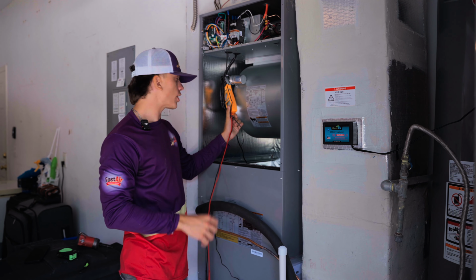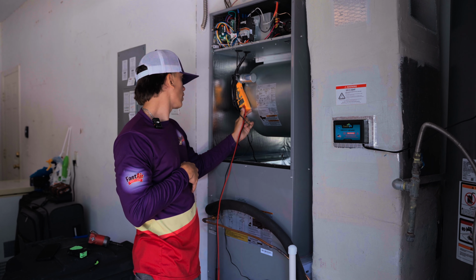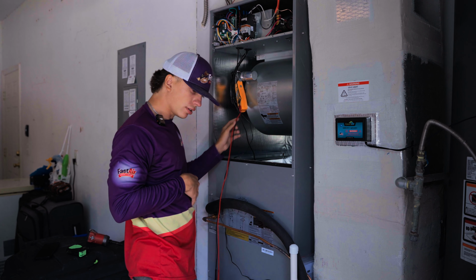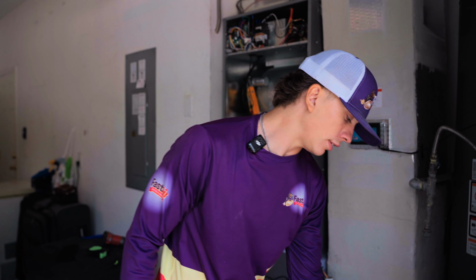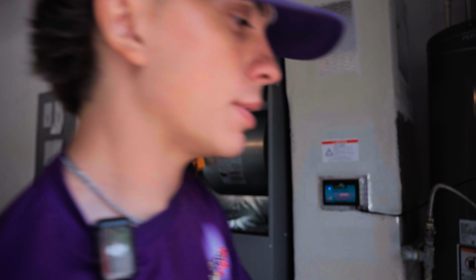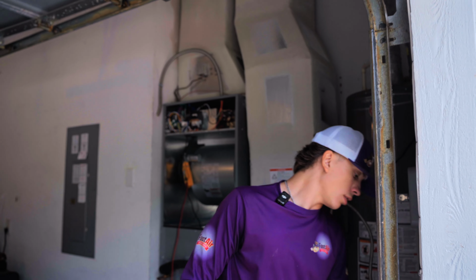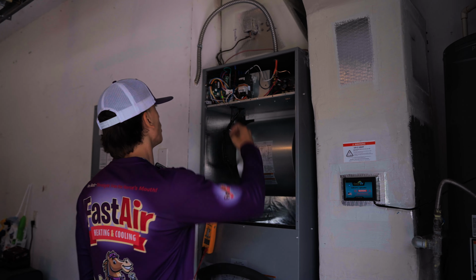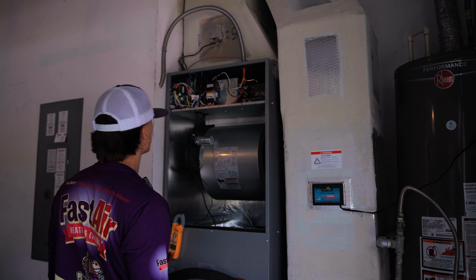Then I go ahead and check the blower amperage, which is 2.11. If we look here at the data plate, it's supposed to be within 3.4, so it's under that, which means it's not working hard, which is good. Next, I'm going to go ahead and shut this breaker off.